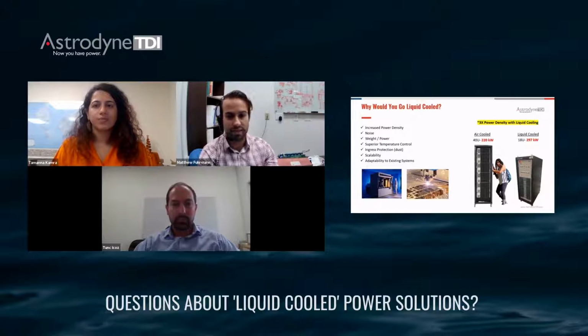The most widely used method of cooling is air cooling, due to its low cost and low complexity. But air cooling does have its limitations. The biggest limitation, and the main benefit for selecting liquid cooling, is power density. The higher the power density, the more heat generation and the more demanding the application from a cooling standpoint. So power density translates to how much power you can fit in a smaller space. For example, you can see here on the slide, we have Tamana supporting the air-cooled cabinet as well as the liquid-cooled cabinet.